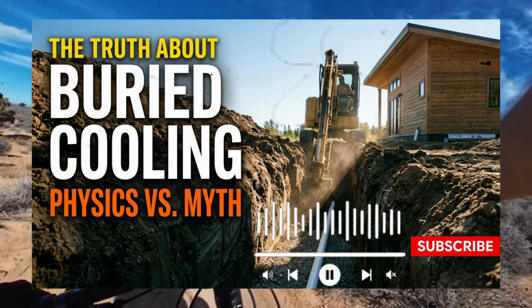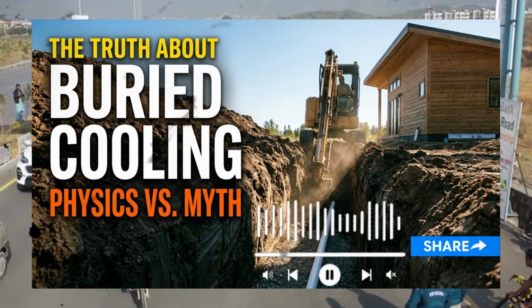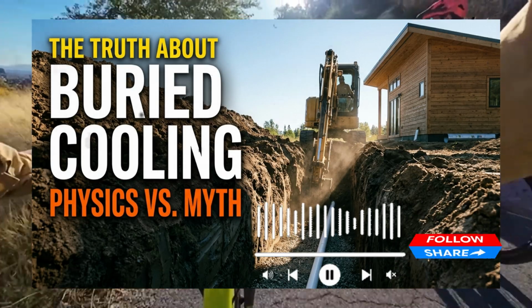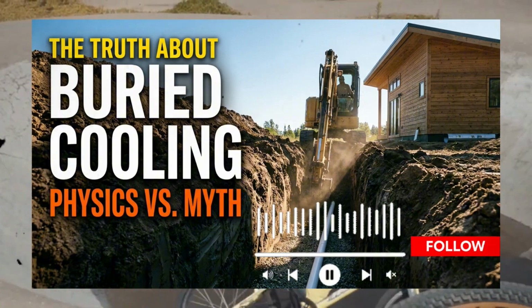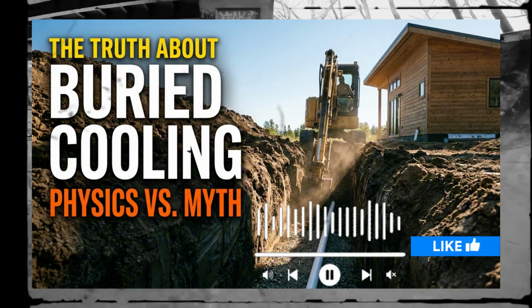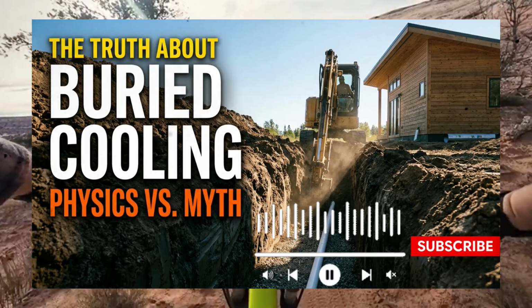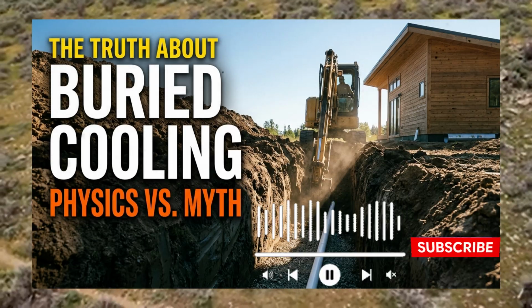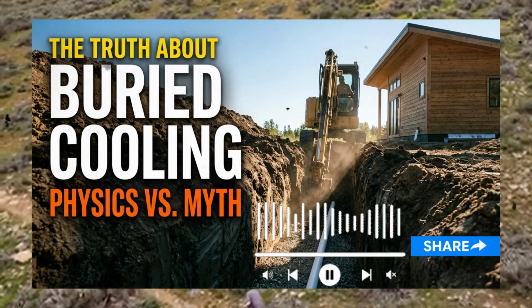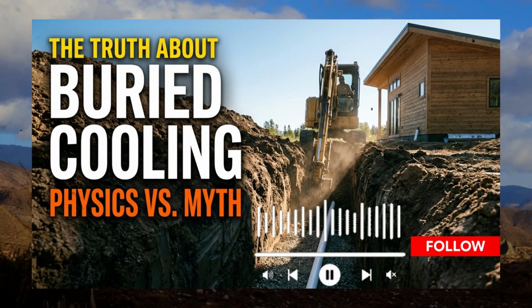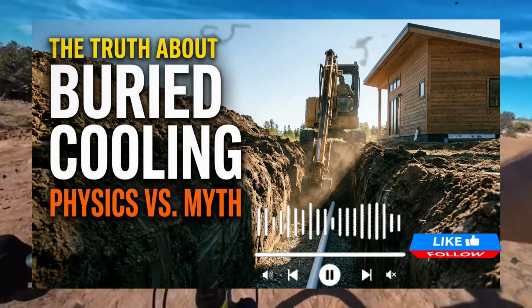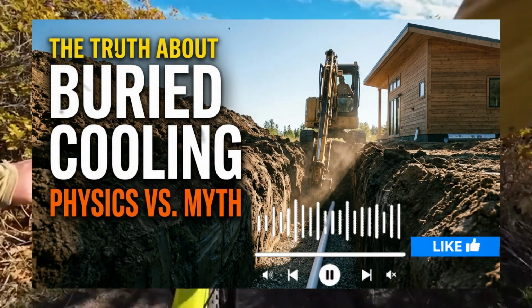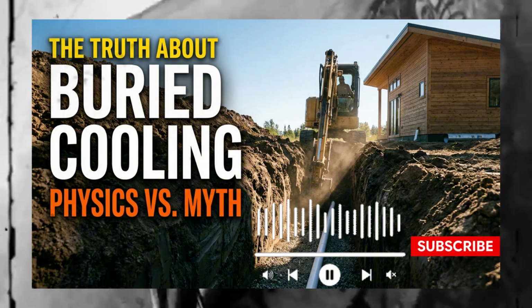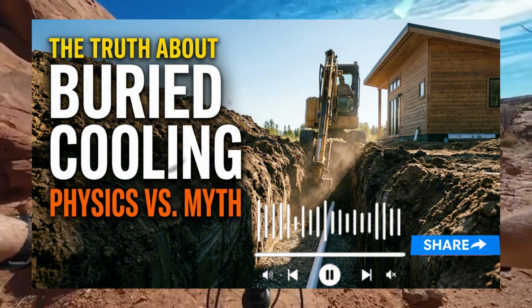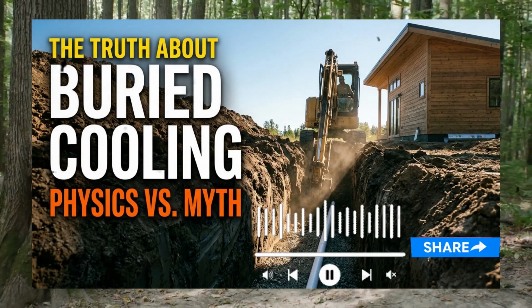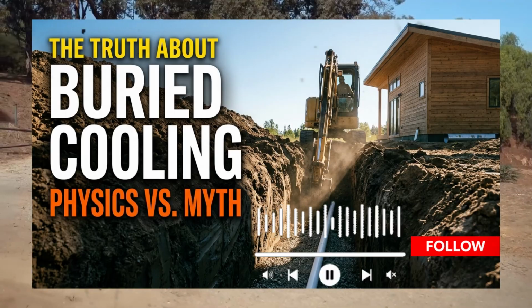Instead, we chose 6-inch, smooth wall, Schedule 40 PVC. It is rigid, incredibly durable, and has a glassy, ultra-smooth interior surface that allows condensation to slide down the slope effortlessly. Assembling these heavy 10-foot sections of pipe in the bottom of a 6-foot trench is physically demanding work. The chemical smell of the purple primer and gray PVC cement was heavy in the morning air as we joined the sections together. Each joint was primed, glued, inserted, and held with a quarter-turn twist to ensure an airtight, watertight seal.